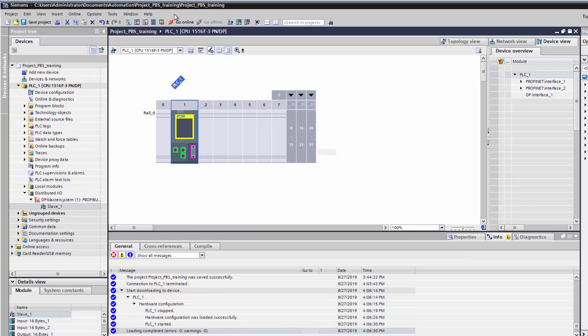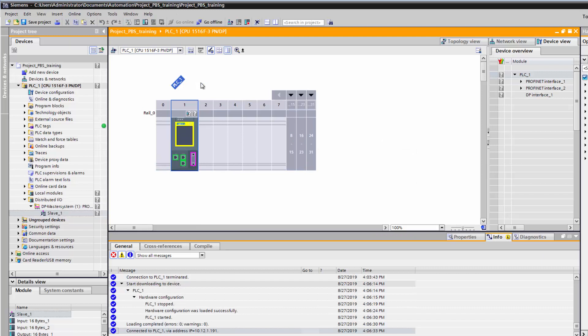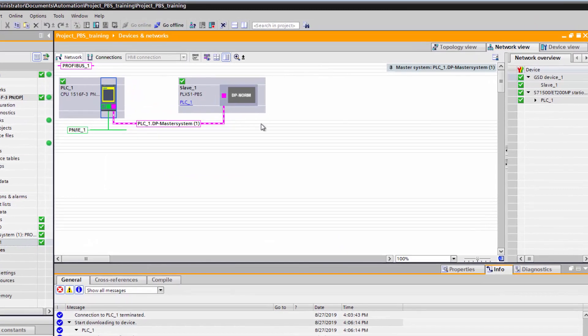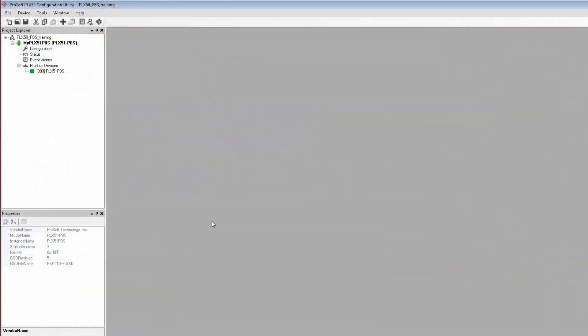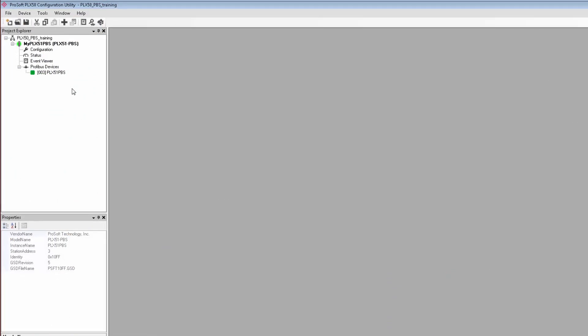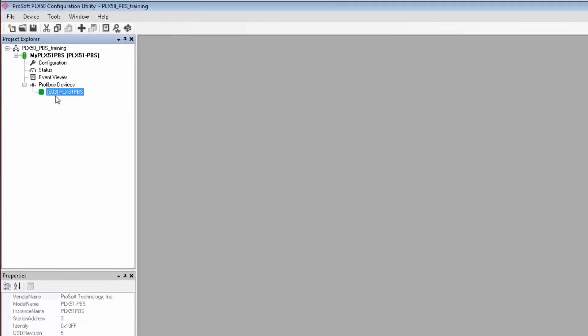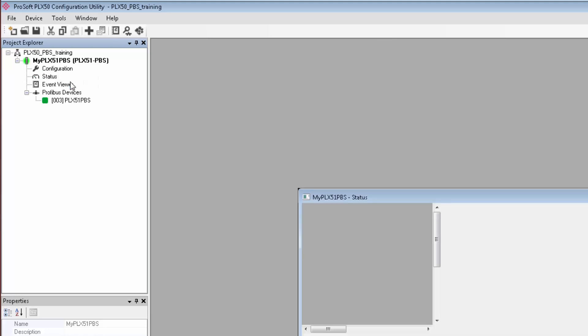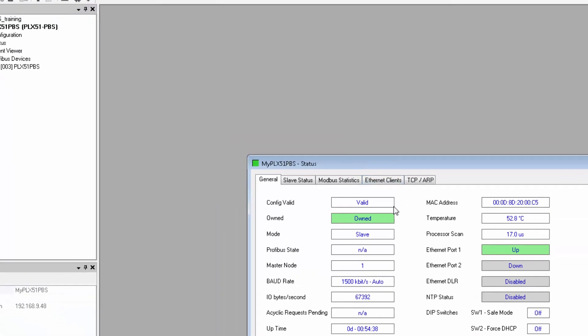Our connection between the S7 processor and the PROFIBUS port on the gateway is now up and running. And if all has gone well, you should see green check marks here. Now if we return to ProSoft Configuration Utility, at this point I can see that my slave devices are showing up green in the Project Explorer view. Everything should be connected and communicating at this point.